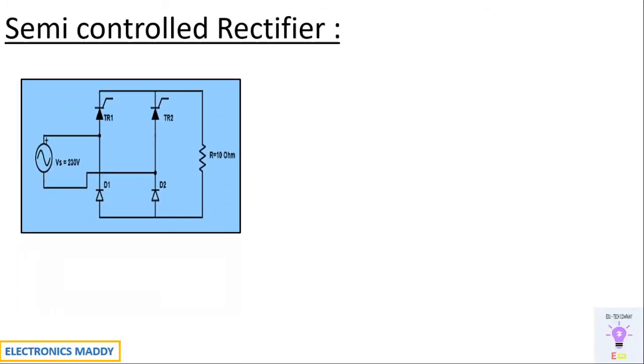So this is the circuit diagram of a semi-controlled rectifier. If you carefully observe, we use two diodes instead of two thyristors. One of the reasons being, if we want a circuit to be operated in only one quadrant, that is with respect to motoring mode, then we will be going for semi-controlled rectifier, as we don't want to spend additionally for the thyristors because the cost of thyristors is slightly higher with respect to diode, and again having additional two thyristors, the complexity of the circuit will increase as we have to control them properly. So that is why we need semi-controlled rectifier.